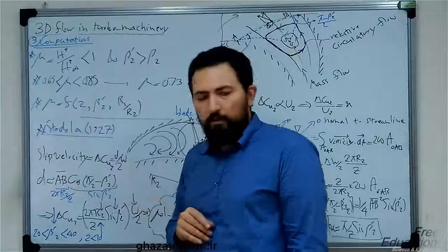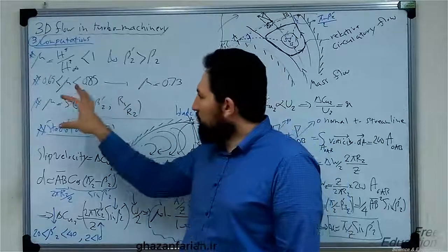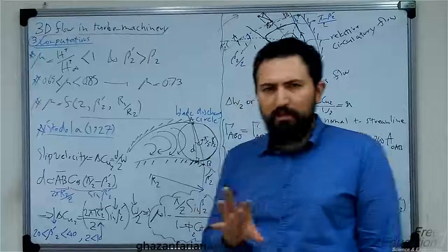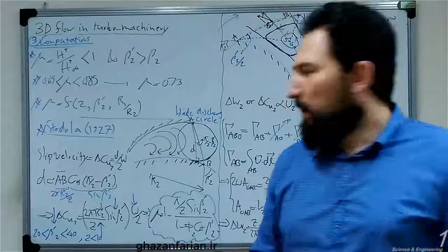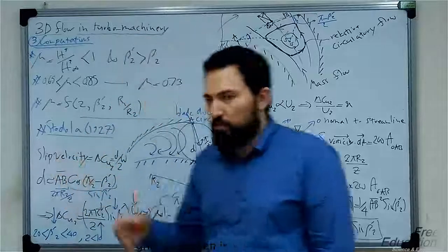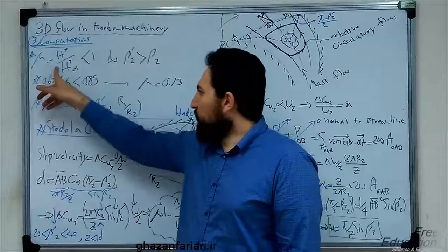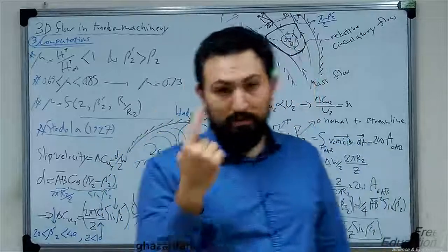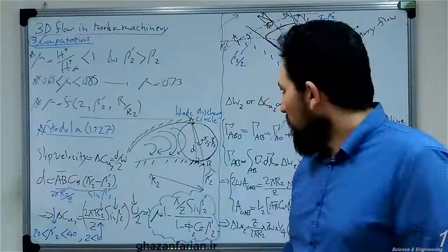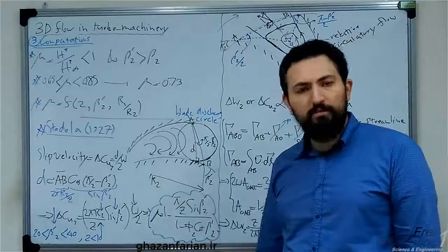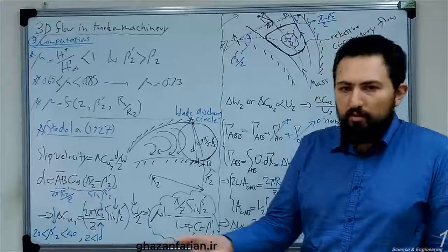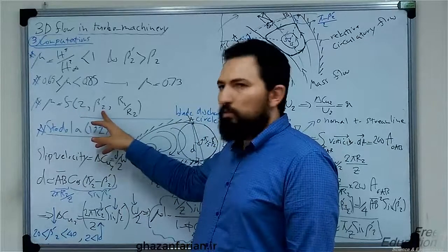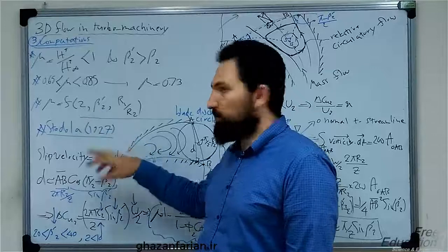The magnitude of the slip factor is something between 0.65 and 0.85. When the flow becomes three-dimensional, the value of the head decreases, so this ratio is less than unity. If you want to propose a single value, Stodola suggested that 0.73 is a good starting estimate. The slip factor is also a function of the number of blades and the angle of the blades at the outlet, or the trailing edge of the blades.